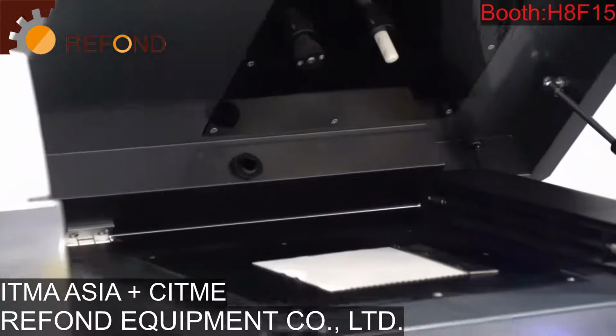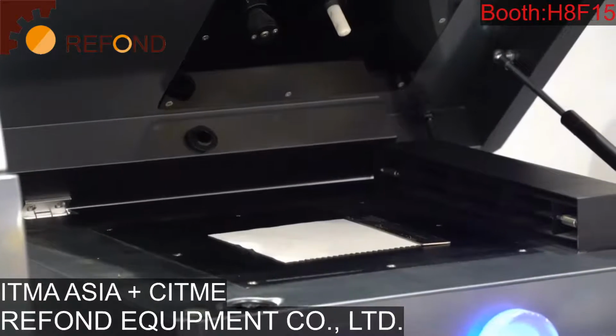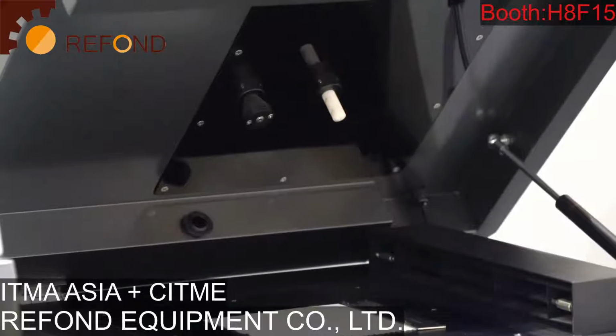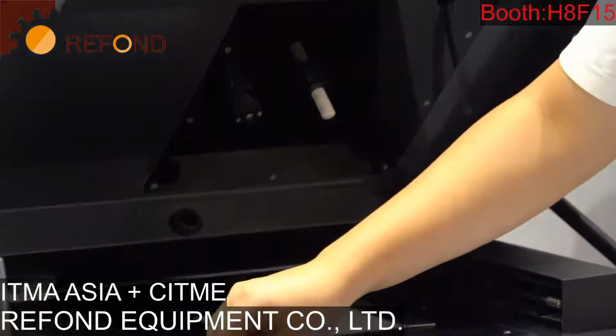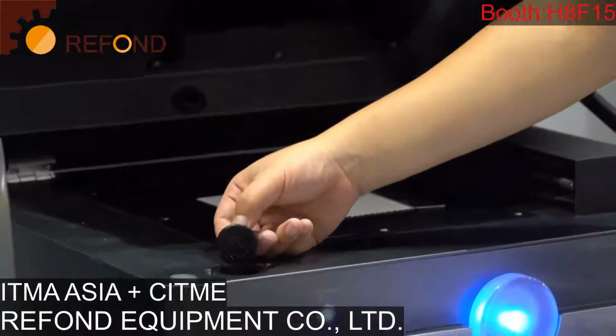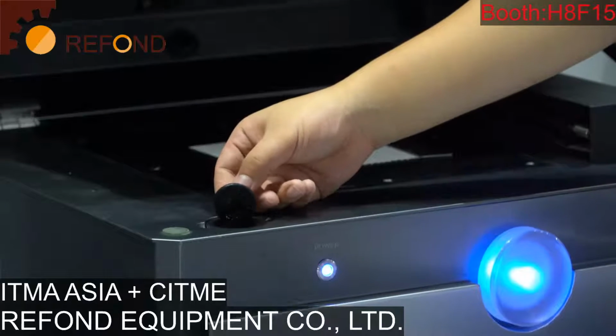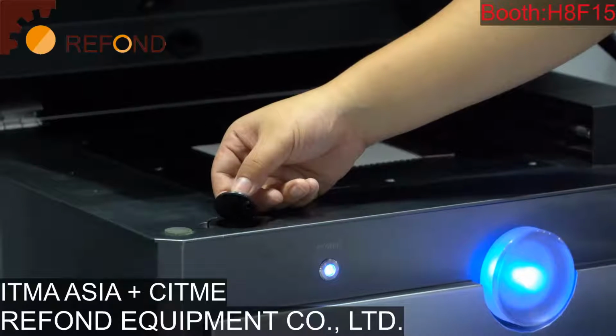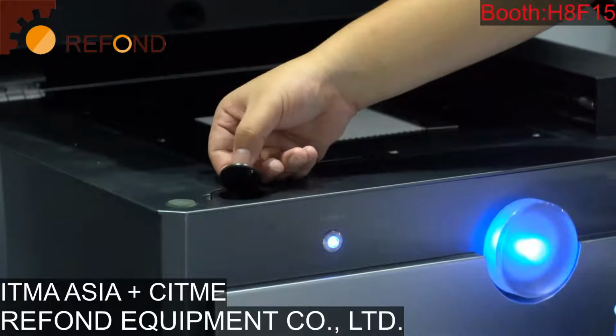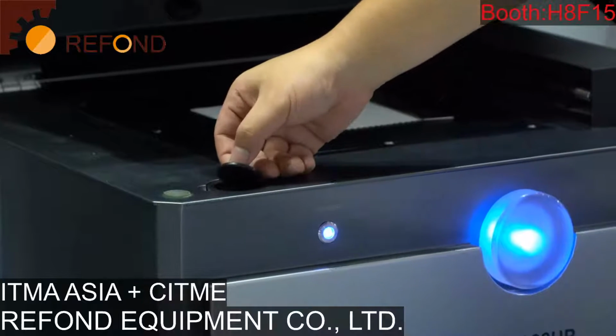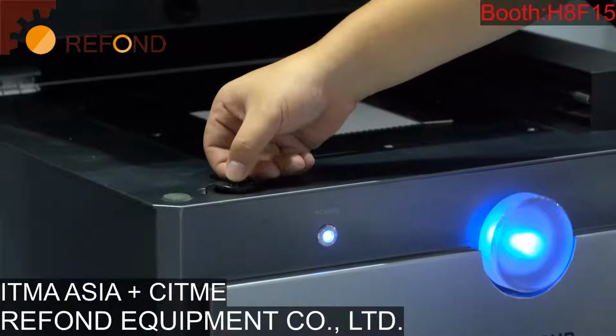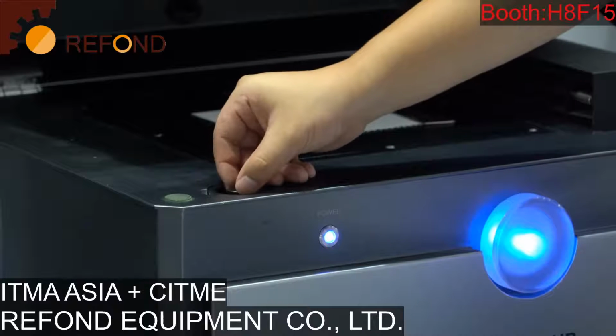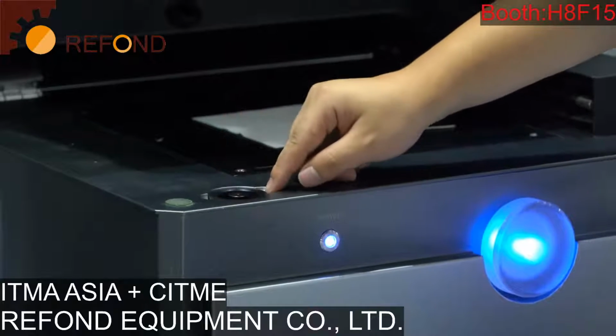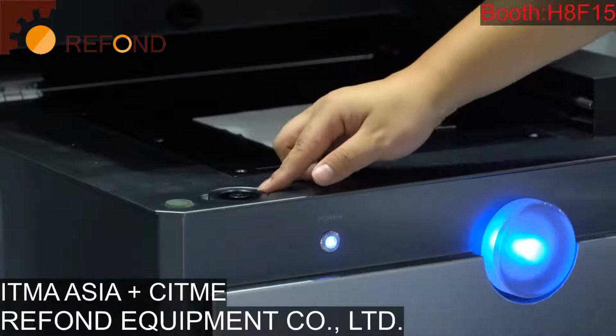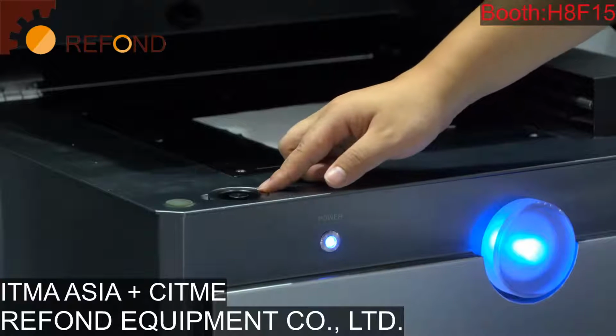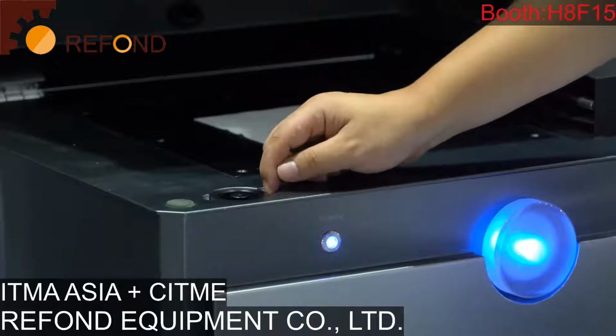The tester has a top cover that can be opened easily. And in the front of the machine, you will see a little cup. In this cup, you should put the test liquid you want to use. In the standard, you need to use DI water for this test. In some cases, for some customers, you can also use artificial sweat for your needs.